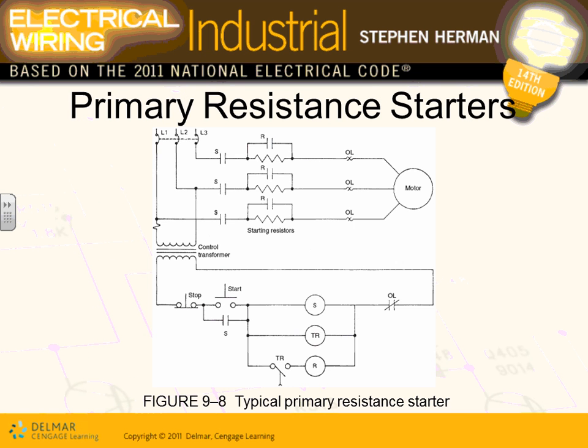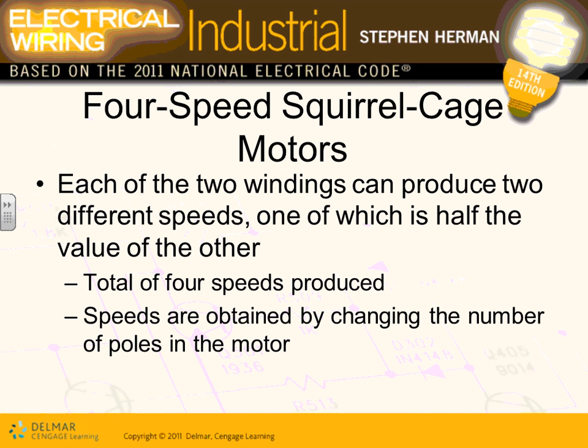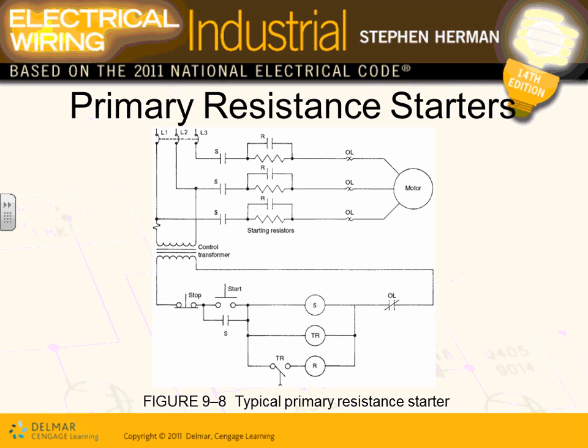Speeds are obtained by changing the number of poles. So, guys, you can have an induction motor with 1 speed, and you can have an induction motor with multiple speeds. The way they do multiple speeds is they have multiple windings. By energizing winding number 1, you get 2 speeds. By energizing winding number 2, you get another 2 speeds, or vice versa. So by energizing different windings, you can get different speeds.